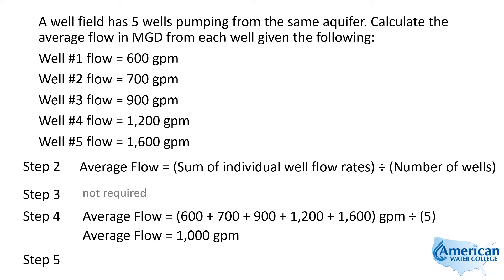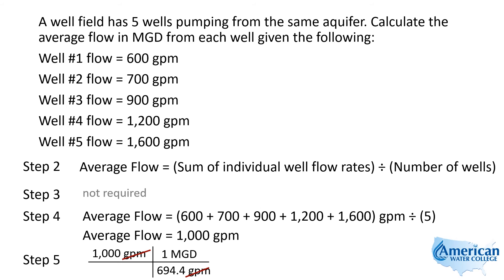Notice they want the flow in MGD. So in step five we convert those units of gallons per minute to units of MGD. We write down our 1,000 gallons per minute and use the equivalent — and this is worth memorizing — that there are 694.4 gallons per minute for every one MGD. So we take 1,000, divide it by 694.4, and that gives us an average flow of 1.44 MGD.